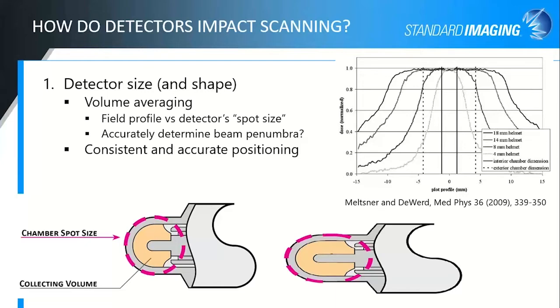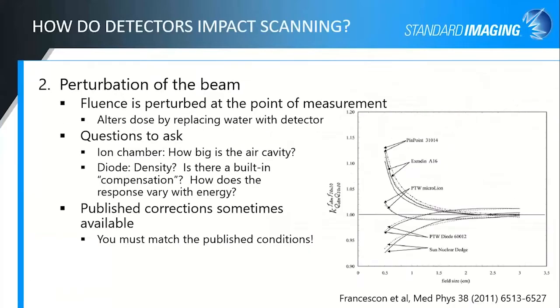volume of your detector. Positioning obviously is a much more critical item with small fields than it is with the larger fields as well. Where a slight offset in the center of your field, or say your PDD scan, is going to make a big difference in the actual measured value that you get. Whoops, wrong way.